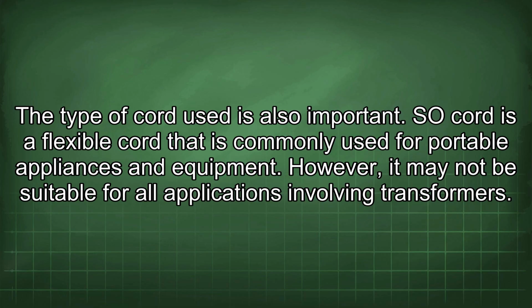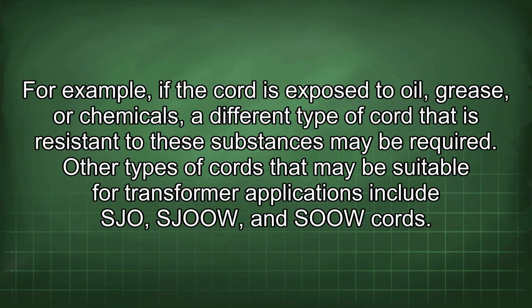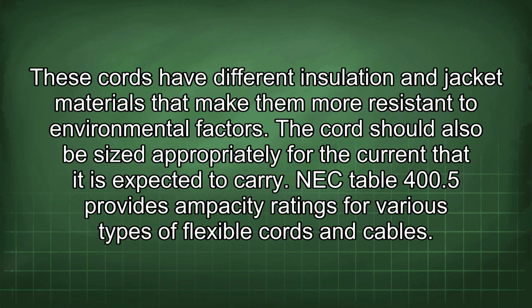The type of cord used is also important. SO cord is a flexible cord that is commonly used for portable appliances and equipment. However, it may not be suitable for all applications involving transformers. For example, if the cord is exposed to oil, grease, or chemicals, a different type of cord that is resistant to these substances may be required. Other types of cords that may be suitable for transformer applications include SJO, SJOOW, and SOOW cords. These cords have different insulation and jacket materials that make them more resistant to environmental factors.